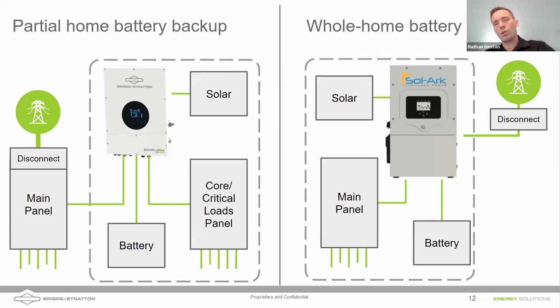Now we have to make sure that the main panel of the home doesn't draw more power than the batteries are capable of, or the inverter is capable of. This inverter is capable of 12 kilowatts of power from batteries and an additional amount of power if solar is also available, producing a total of 15 kilowatts of output from solar and batteries in a grid down situation.